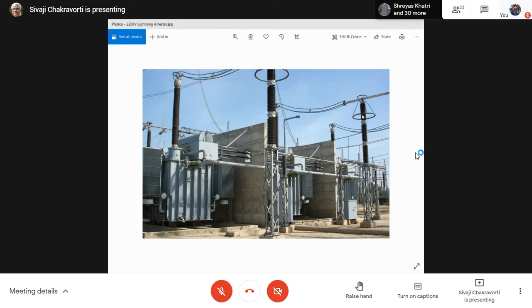This part of this component is having some series capacitance formed with respect to this toroid. And therefore, this series capacitance is increasing. And that helps in linearization of the potential, not through the entire length, but only through that first part.